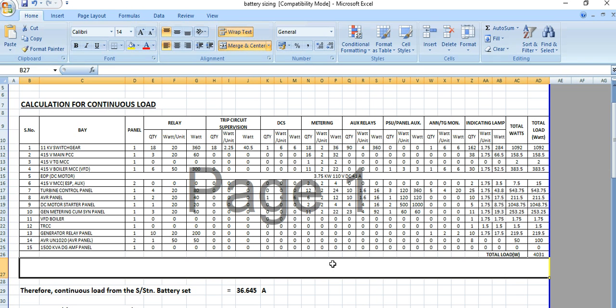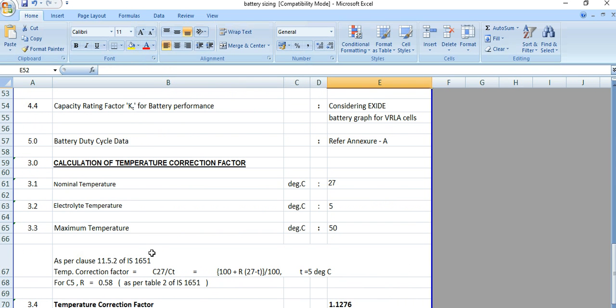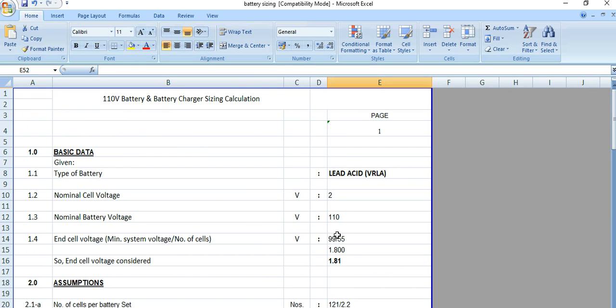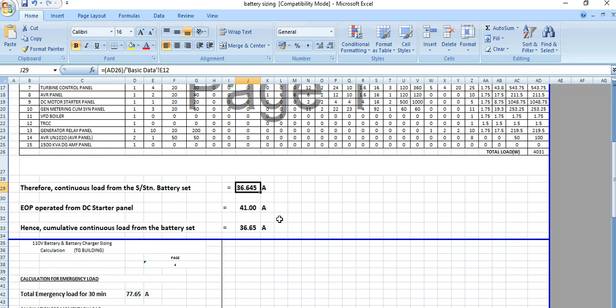The total continuous load required during normal running condition comes to 4031 watts. The continuous load current from the battery set is calculated as 4031 divided by E12, where E12 is the nominal battery voltage of 110 volts, giving 36.645 amperes. The EOP operated from the DC starter panel requires 41 amperes.